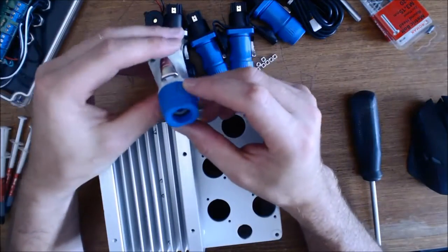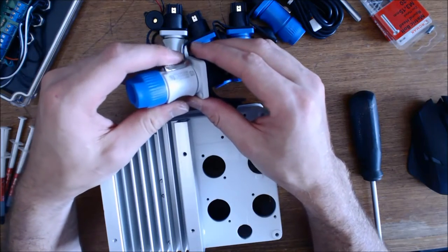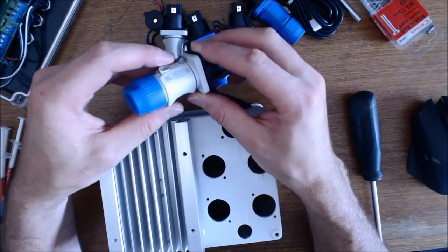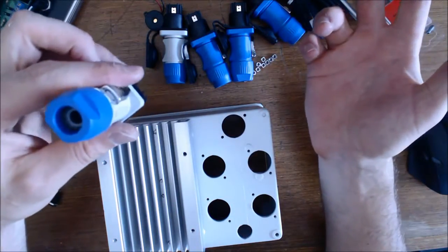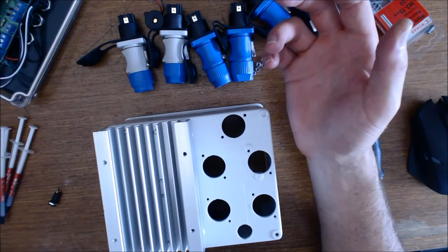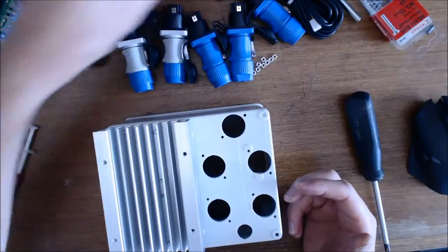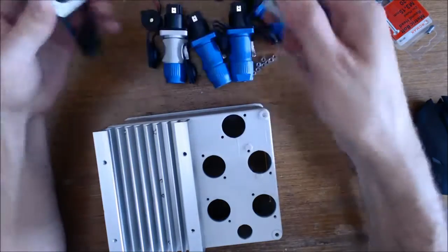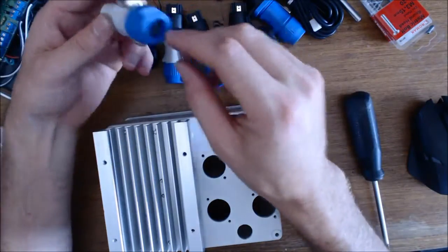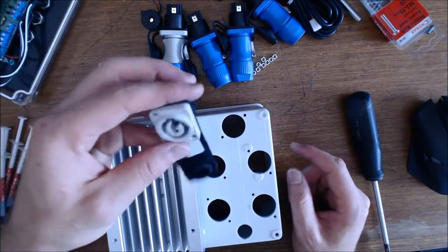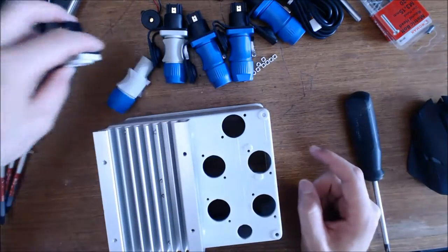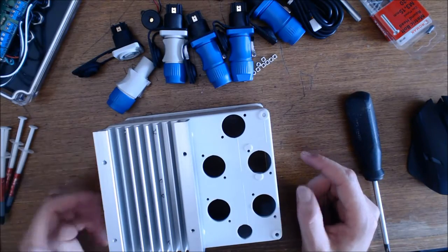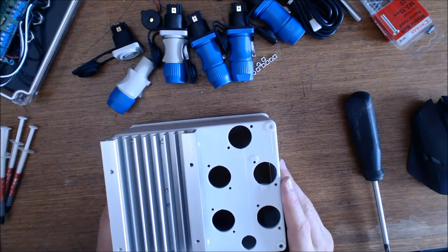So what we're going to do now is we've got our power units. These are our power units rated to 20 amps, and at 20 amps they will heat up substantially by about 20 to 30 degrees, so if you are running that much power through there, then make sure that you are comfortable with it and your electrician is comfortable with them being used in that manner. All of these supplies, basically you need to determine that you're comfortable using them as has been specified. These ones are IP65 rated, and they are just fantastic. There are seals inside the body, there are seals at the back of the body and the cable gland to stop any water and dust getting in. In the inside of here, there's actually a silicon O-ring in right at the back. They are very, very well constructed, I'm really, really happy with them.